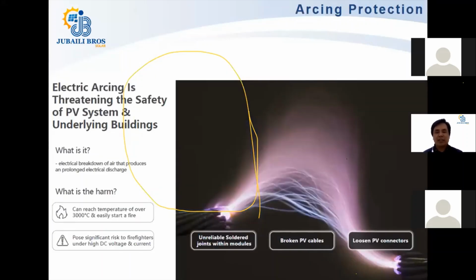Huawei provides you the arcing protection with this range, with all its inverter range. The arcing protection, as you know, is required for events such as where there are unreliable solder joints within modules. There can be broken PV cables. There can be loosened PV connectors. In such cases, the loose cables can still transmit current through the air. When that happens, there can be a temperature rise of up to 3000 degrees Celsius. And if there is something flammable nearby, that can get burned. It will not only damage the PV system, it can also damage the asset, which is your building.